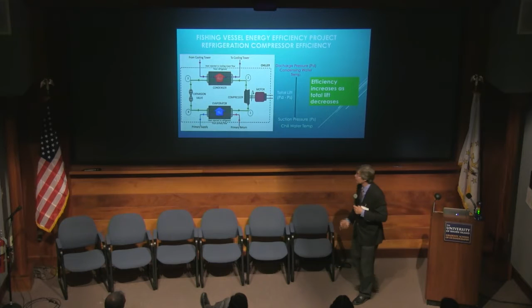So we looked at it and asked, what can we do about it? Well, we decrease the discharge pressure by putting more cooling water flow through the condenser, and that lowers that lift down. When you do that, you can see your efficiency improve. This is from the manufacturer of the gear on top. So EER is the same as the COP.